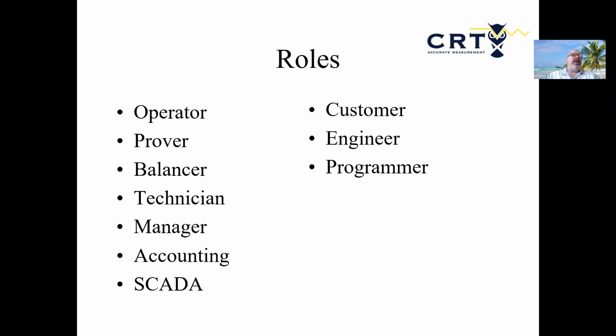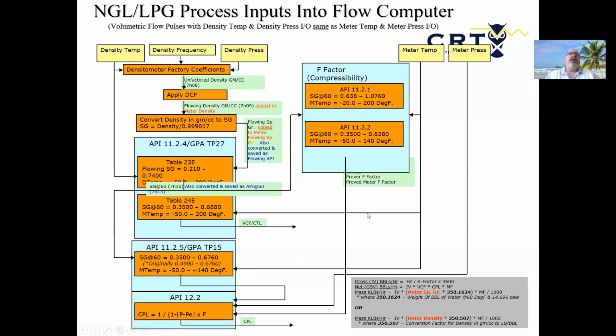So why do we have all these roles? Again, this is just process inputs into a flow computer: taking volume pulses with density and temperature, and how we turn that temperature, pressure, and pulses coming in into gross barrels, net barrels, mass pounds, and flow rates. It's how we use the tables, how they convert out, and each step along the process in coming up with an actual corrected volume. So they're pretty complex processes inside there.